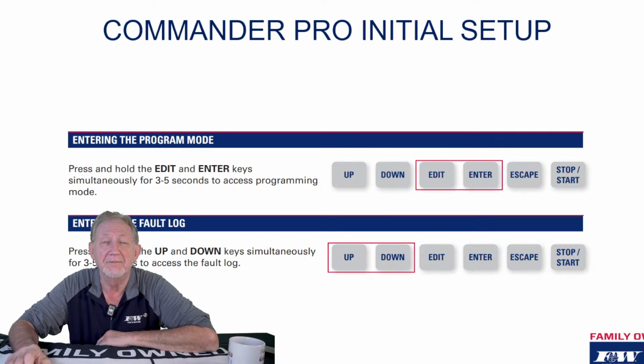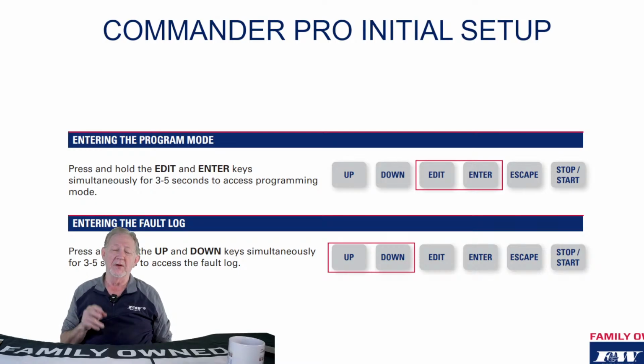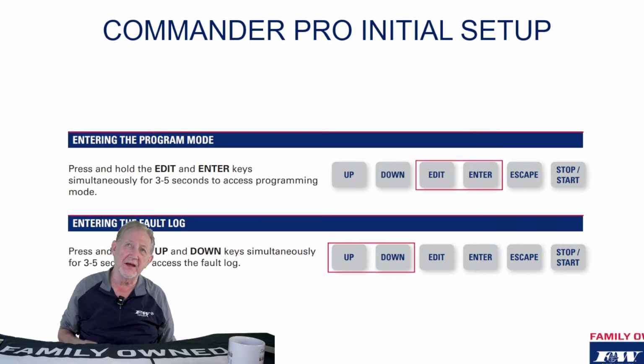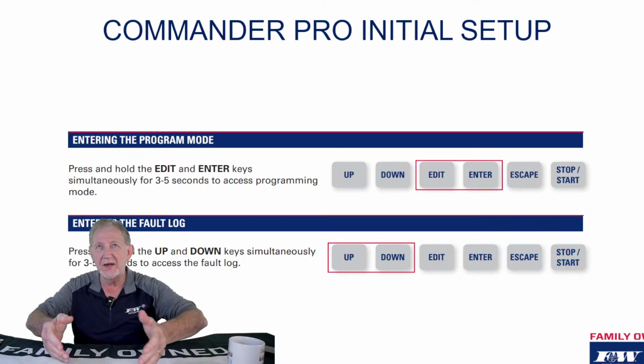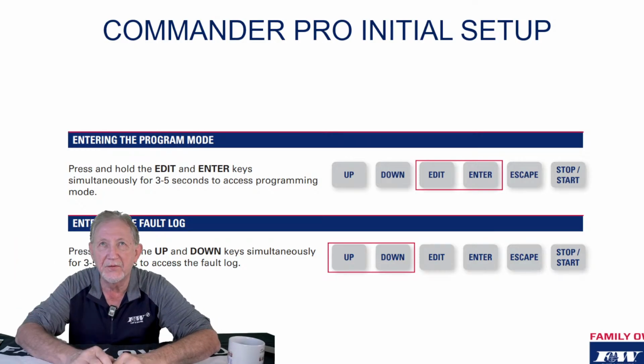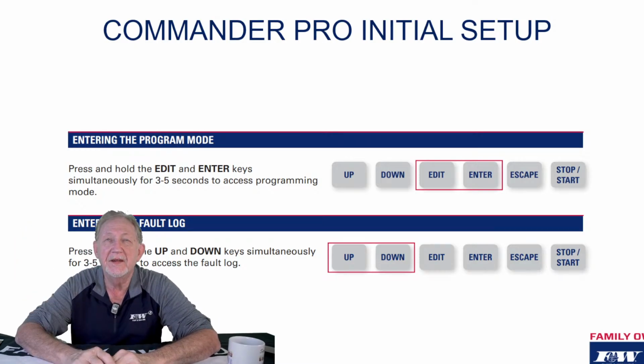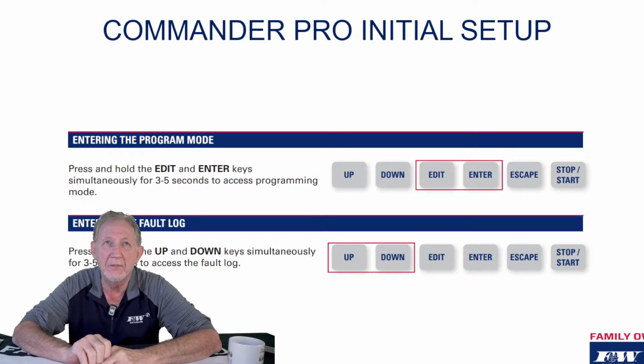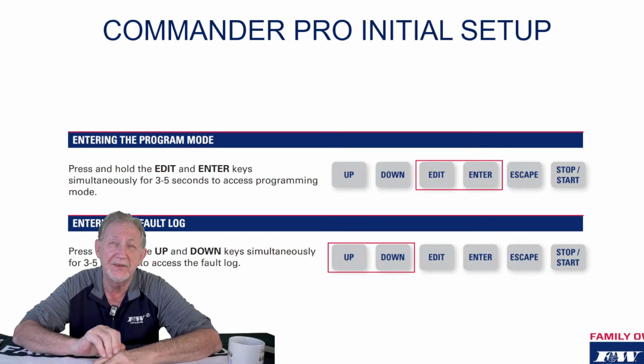The edit and enter button. This is what you're going to need to do to get into the drive programming. You're going to need to use 2 fingers, press that edit, enter button simultaneously, hold it down, I don't know, count to 3, and release it, and then bingo, you're into the programming mode. Now the reason that that's designed that way is just to keep inquiring minds out.